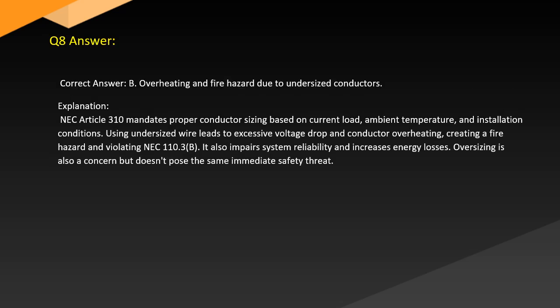Answer. Correct answer: B. Overheating and fire hazard due to undersized conductors. Explanation. NEC Article 310 mandates proper conductor sizing based on current load, ambient temperature, and installation conditions. Using undersized wire leads to excessive voltage drop and conductor overheating, creating a fire hazard and violating NEC 110.3(B). It also impairs system reliability and increases energy losses. Oversizing is a concern, but doesn't pose the same immediate safety threat.